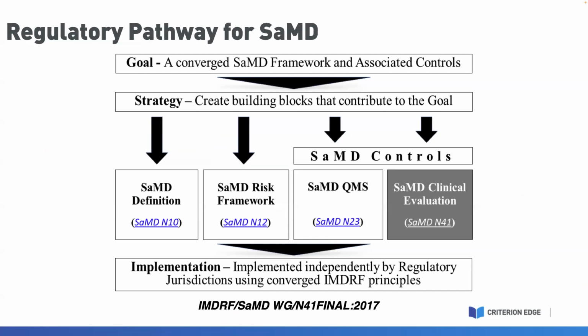But for that high level overview, if you're just getting started and trying to get sort of a lay of the land, the document that I've included down there at the very bottom of this slide, that final document from 2017, really provides a very good overview. Overall, this document is encouraging manufacturers to use some of these same principles that we apply to any medical device to help us better understand how to modify software and to take into account real world performance. And that's really the goal of putting it under the same regulations as any other medical device.